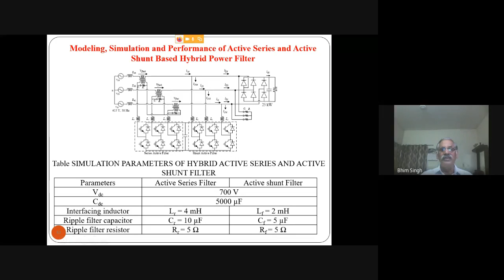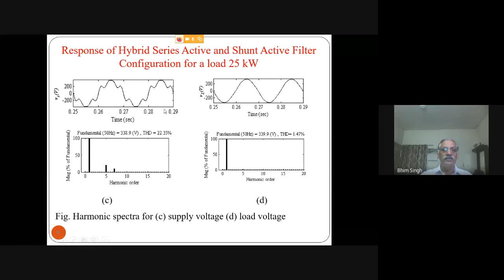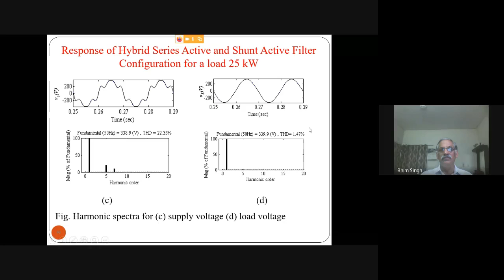I already talked about the design example, and typically the waveform in the enlarged form. How much are we able to achieve? You might have a THD around 80%, but your grid current THD is reduced to around 2.18%. Your voltage distortion is like 22%, but the load voltage distortion on the grid is around 1.47%. Also, it's able to do it.